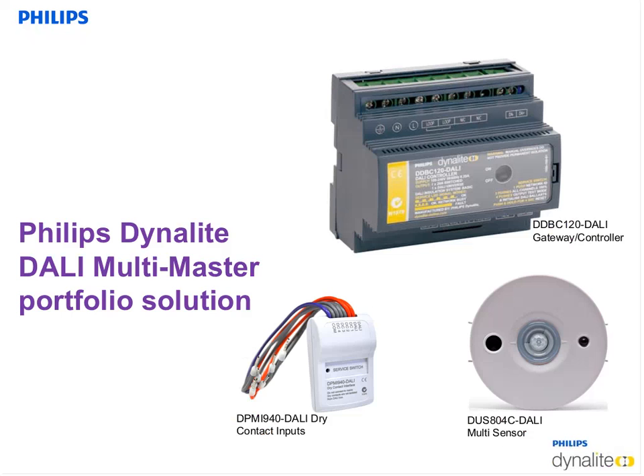A dry contact is simply a device which allows other switching devices to communicate with the dynet network. For example, a security alarm needs to send a signal onto the dynet network, so the dry contact converts that signal into the dynet network. You might have a magnetic switch. Remember I mentioned these partition doors? Well, you need a dry contact to convert the magnetic switch input into the dynet network.